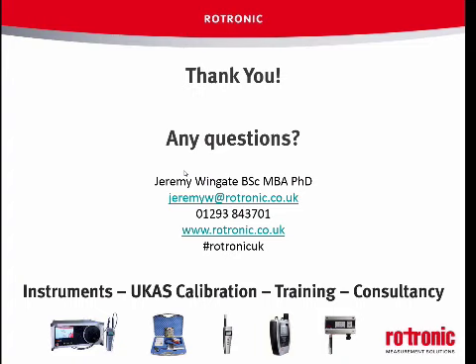Yeah, it's a good question. This is where my building control knowledge falls away. But in principle, you would not want to measure the humidity where you're getting saturation. Where there is liquid water around, there's no point measuring the humidity there. So if you did have an area of the system with this cooling in place, you would measure the humidity far enough away from that, beyond it, once the air has passed through and cooled down. Any moisture in it has then gone back to vapor, probably as the air warms back up a little bit, and you would measure the humidity there. You may be surprised, it may not be anywhere near 99% or 100%, but you'd certainly want to always avoid sensors condensing. It's a good example of not putting a very cold sensor in a hot, wet duct, because it will act as a condenser straight away, get saturated, and take a long time to dry out. Sensors that get wet stick at 100%. They can stick there for quite a long time.